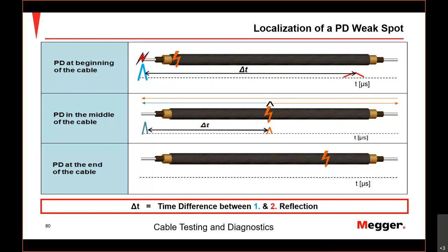Actually, this looks just like our calibration pulse from the pictures before. You have a first pulse that didn't travel very far, so it's a sharp, narrow, slim peak, and it arrived very quickly, so it's still high. I call the other one the little brother, because they come from the same discharge, right? That little brother had been traveling a long way, so it saw a lot of attenuation. Traveling through the cable, you lose all the high frequencies. That's why it's a small, wide little brother. And these two belong together.